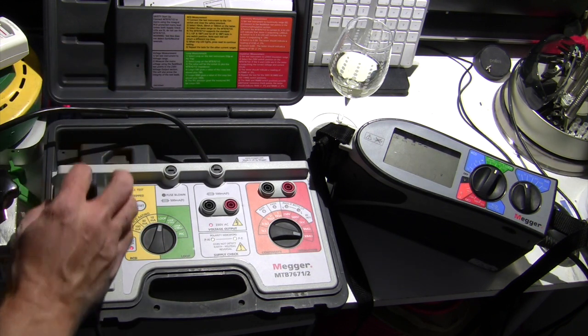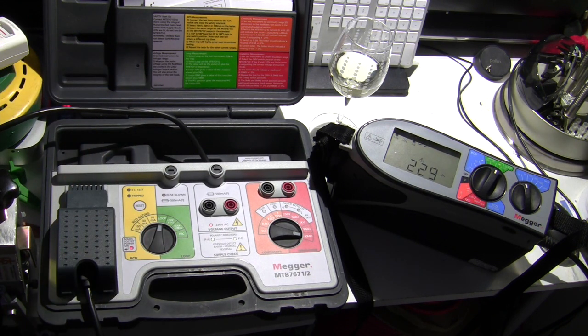So I'm going to switch this to loop, and I'm going to close the socket there to kick it off. The Megger kicks this test off automatically, unlike the Fluke, which you have to press the test button on. It gives you that beepy warning and then off it goes, and we can see it's actually come up with quite a high number there, 1.43. Now again, that's because I'm on an extension lead.